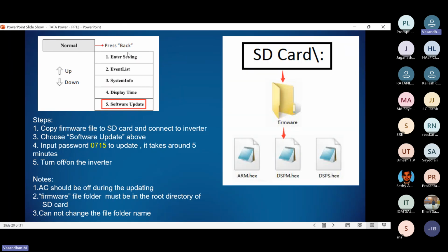There are 5 options here, the first 4 already explained. Fifth option is software update - for example, if a customer has some issue with the inverter, like software OCP meaning overcurrent protection issue. There are 144 fault codes for the inverter. Taking one example, for software OCP current detection, there will be one specific file and software version that we can share with the customer.